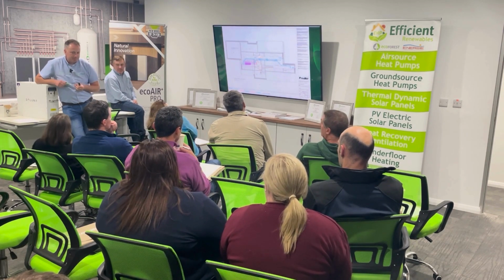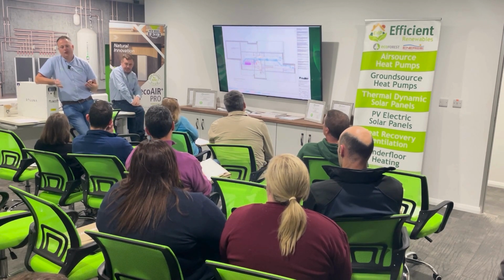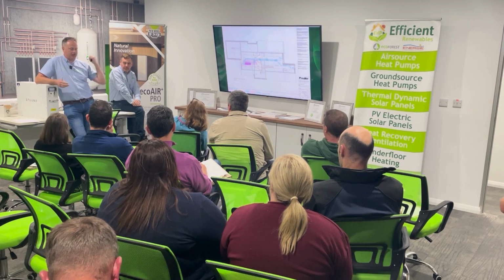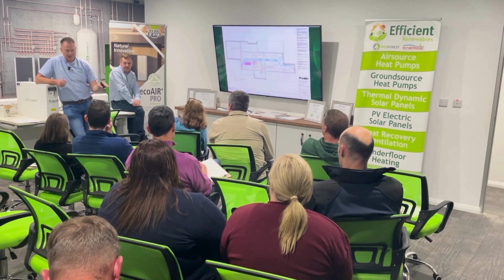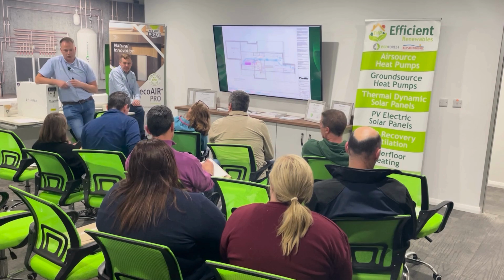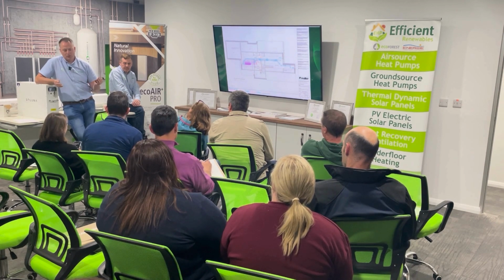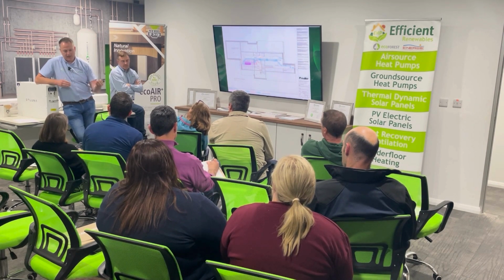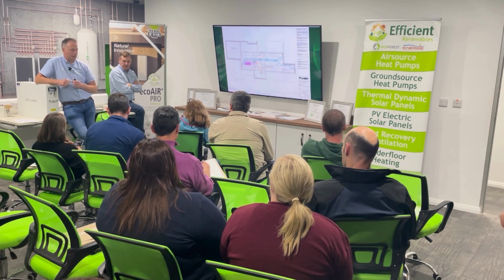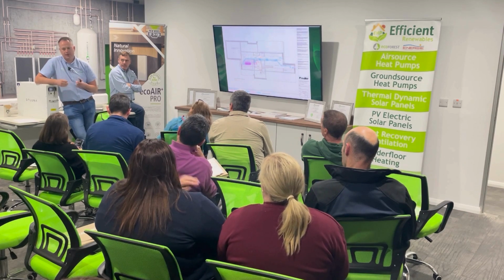For underfloor heating, what is the most efficient flooring option on top of that? If we start at the start, polished concrete. We've polished concrete down in what I'm going to say is our old part down here, done 4 years ago. This was done last year. This is printed concrete, and then you've got your stone tiles, then just your standard porcelain tiles, and then laminated wooden floor, carpets, solid wooden floor. So tiles are the best, but most houses that we're doing, it's tiles and laminated floor and semi-solids, and it all works fine with that. We would have underfloor heating operating in houses with carpet that thick there, but you lay the underfloor heating slightly differently and adapt it to suit the needs of the client.